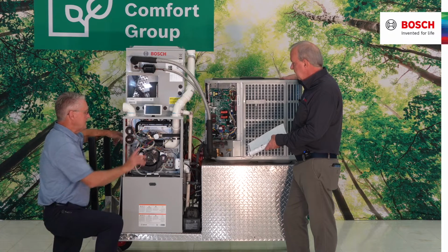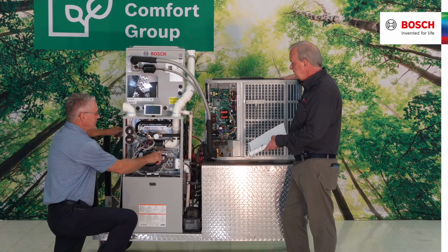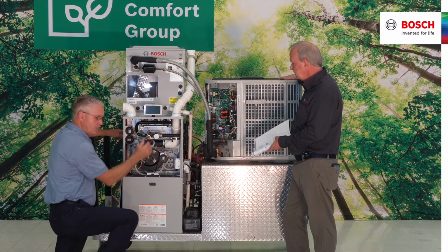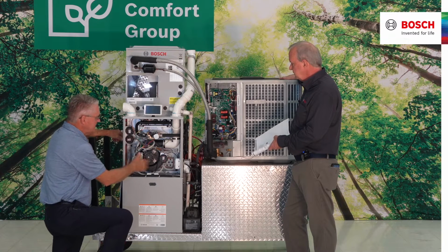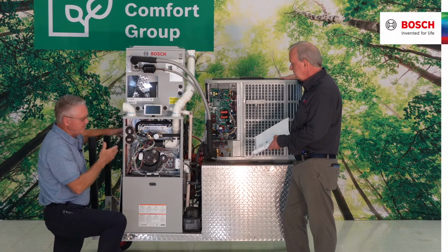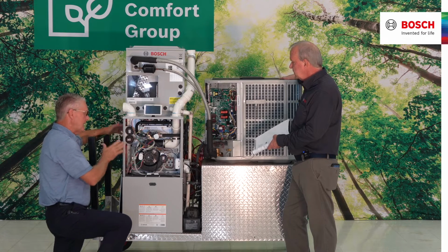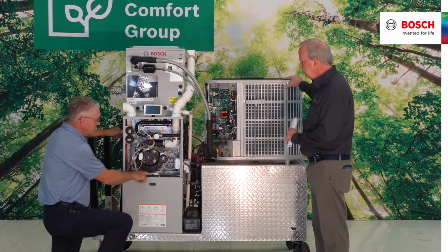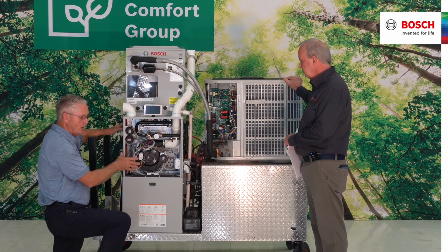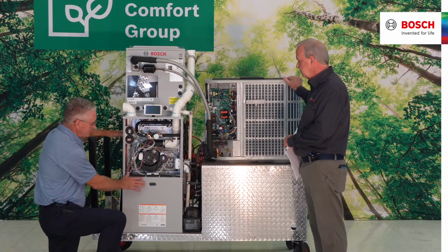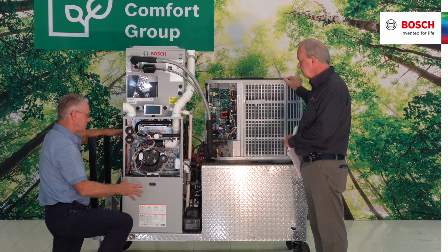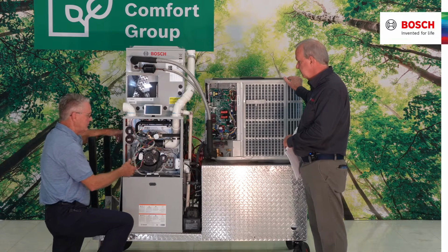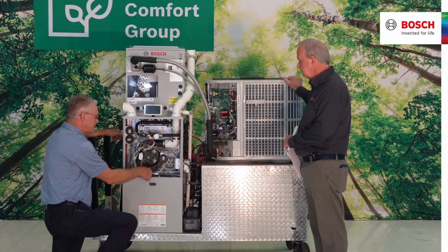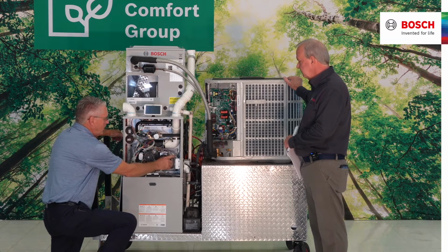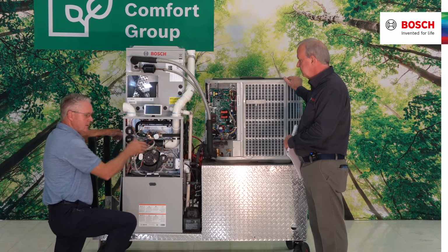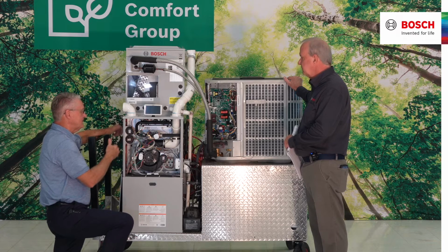Let's go back just a little bit and make sure I explain this black and white, what would be the power wire to the furnace. This particular furnace is a 120 volt furnace, meaning I've got a hot and a neutral for the 120. The door switch down here is a protection part of this furnace, meaning I can't run this furnace with the fan compartment opened up and allow combustion air back into the ductwork. That L1 is passed through that door switch, and L1 is always tied to the black wire, meaning this is a polarity sensitive piece of machinery.